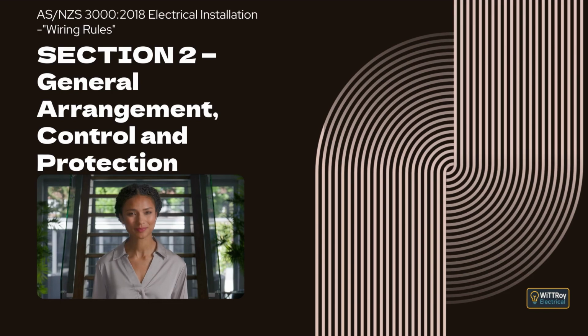Clause 2.5.5.1, general. This clause explains when we must protect switchboards from internal arcing faults. An internal arcing fault is a very dangerous fault that creates extremely high temperatures, pressure, and burning metal. It can seriously damage equipment and put people at risk. Protection must be provided whenever a switchboard is rated at 800 amps or more per phase. This applies whether the switchboard is operating normally or being worked on.